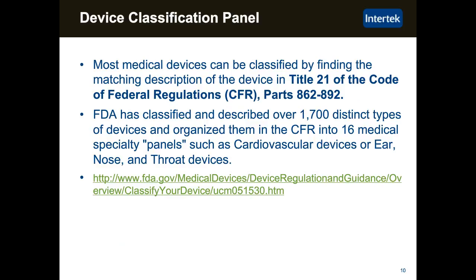So most medical devices can be classified by matching the description with a section of the Code of Federal Regulations, specifically Title 21 and Parts 862 through 892, where they basically describe the different types of medical devices. Over the years, the FDA has classified and described over 1,700 distinct types, and they've organized them in the Code of Federal Regulations into 16 specialty panels, such as cardiovascular or ear, nose, and throat, or orthopedic and other types. On the slide deck, there is a link that will get you to a guidance document on how to classify your device.